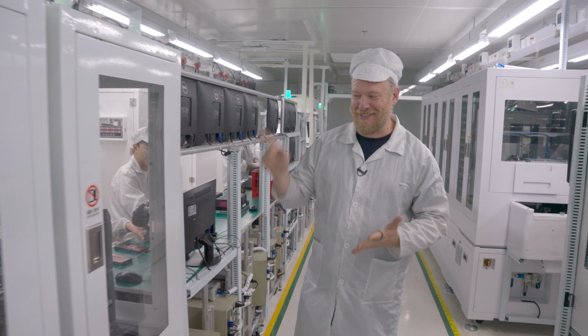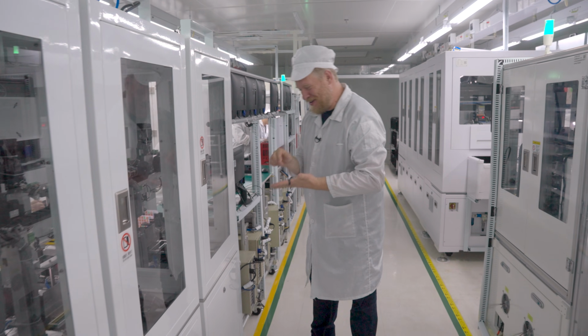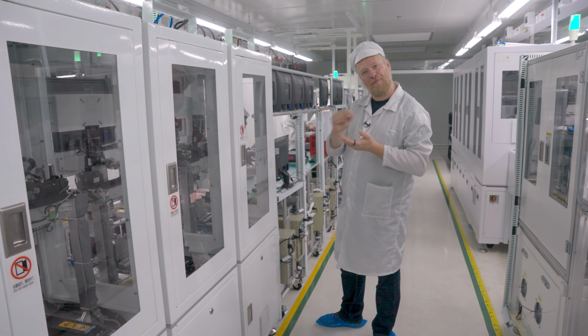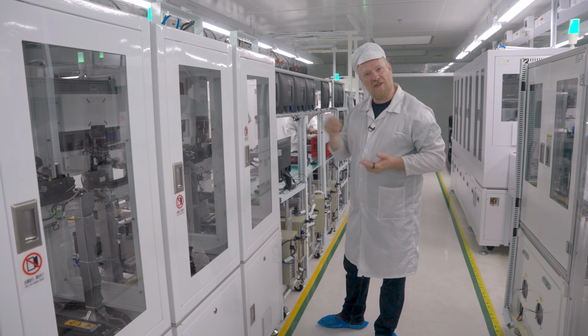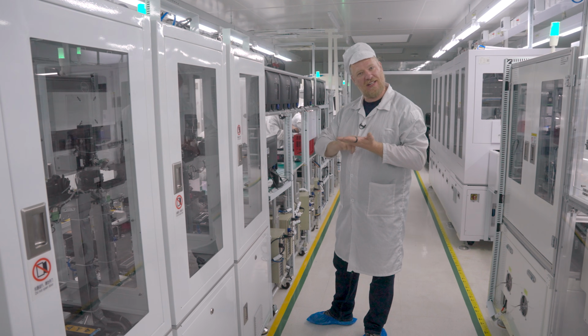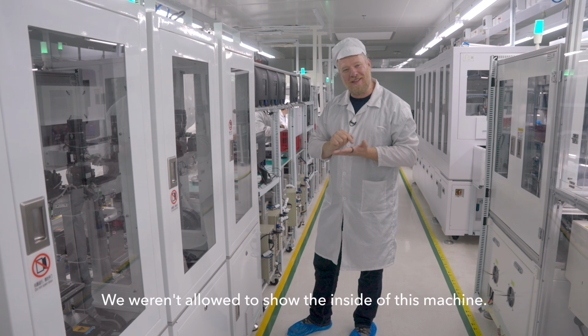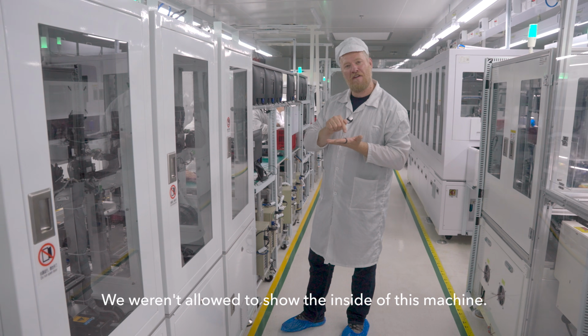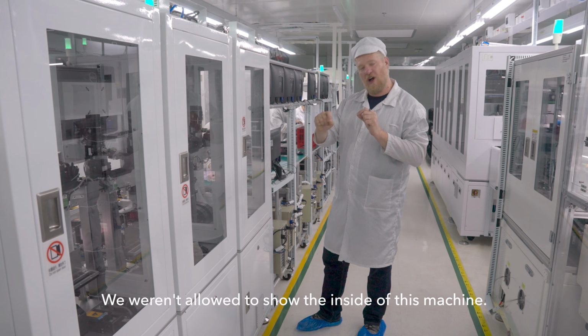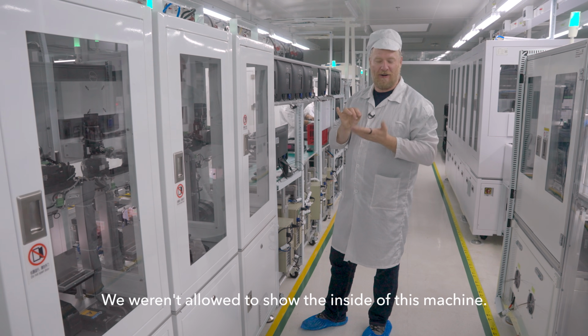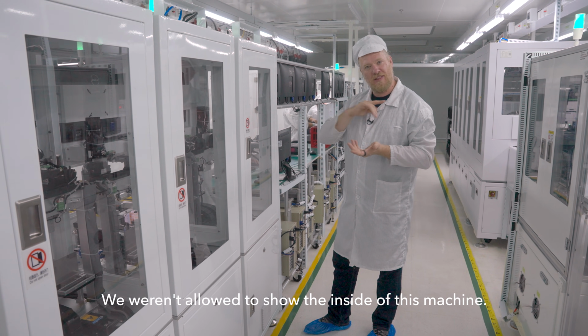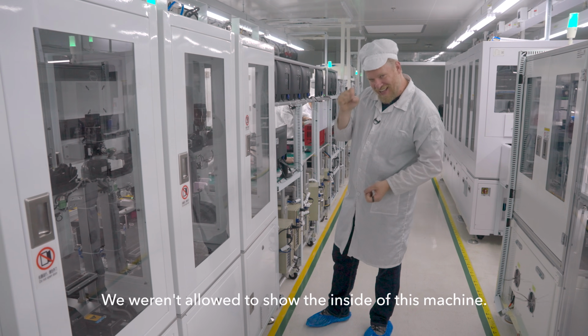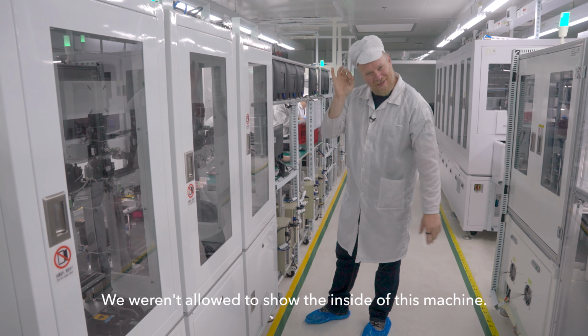These machines are pretty cool. We talked about that snap key button, and they've got a quick action button as well with pressure sensitivity. This machine simulates a finger, tapping on 5 different pressure points along those buttons to make sure they're sensitive along the whole length. They've essentially got a little probe coming in there simulating a finger.